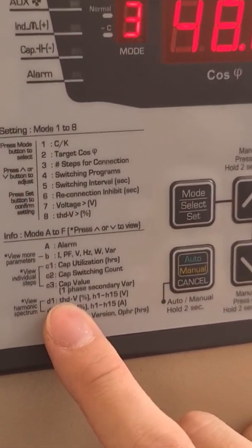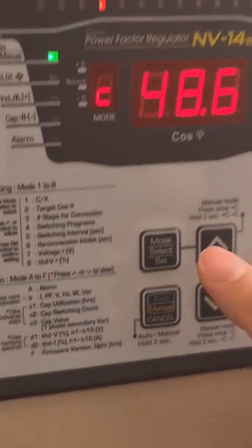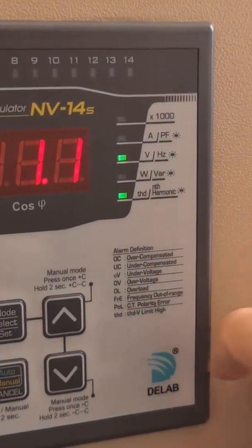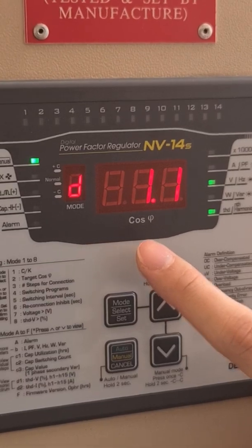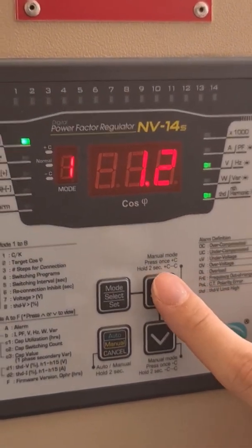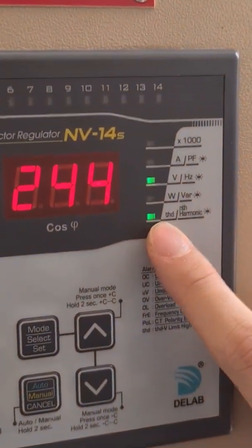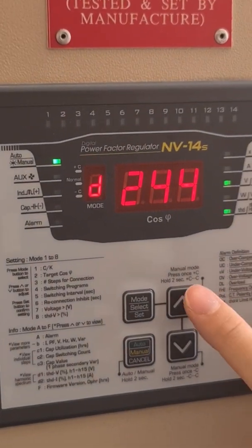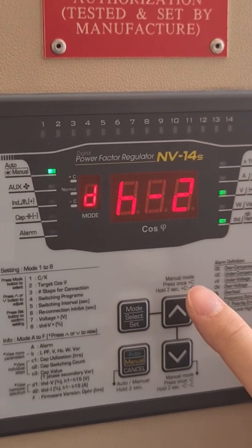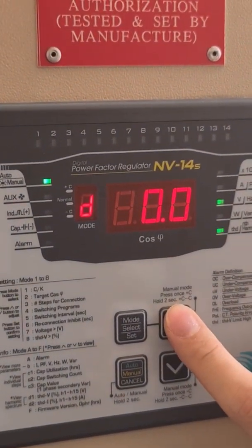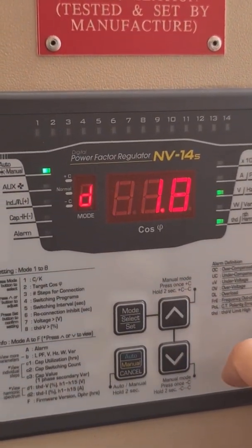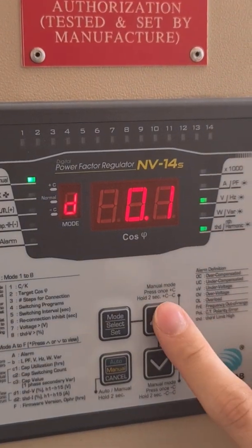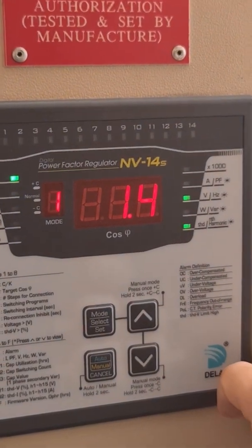Next, I want to explain the THD voltage parameter. By pressing the mode button again, it will display Mode D1. When these two LEDs are not flashing, it means it is in THD voltage mode. The current THD voltage is around 1.1%. When you press up, the LED will flash, indicating harmonic spectrum mode. You can then scroll through the first up to the fifteenth harmonic spectrum for voltage.